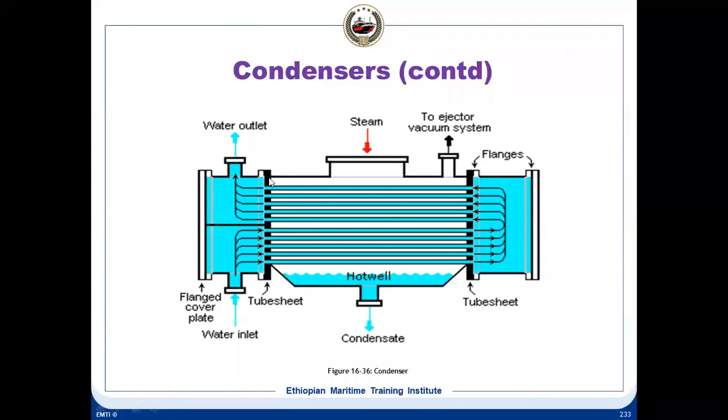and bolted to each end of the condenser shell. So this could be bolted on, and then you will say, how can both ends be bolted on? Okay, this end is bolted on, then the tubes are inserted in these tube plates, and then they are expanded. You have the tube expanders, then the tubes are expanded in place. Once they are expanded in place, these bolted tube sheets cannot be removed without removing the tubes also.